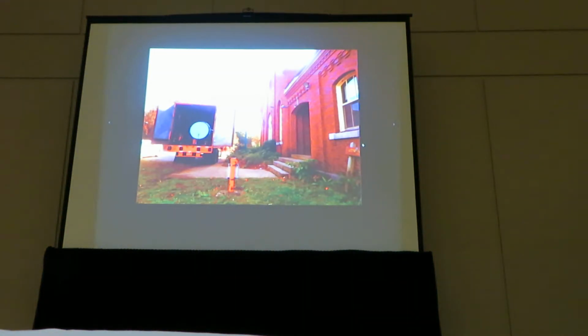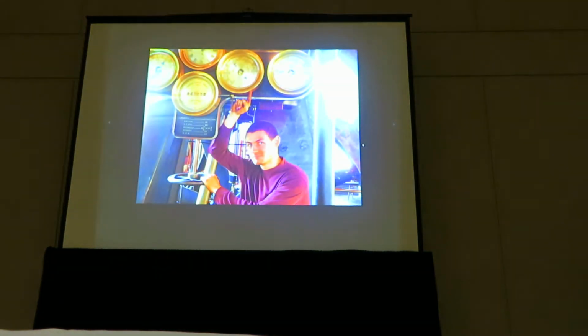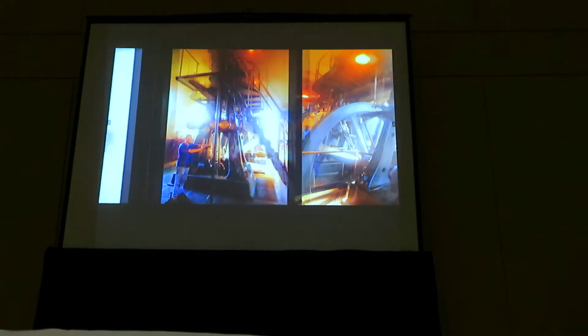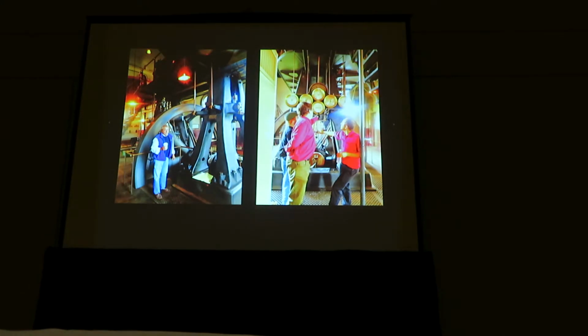And then another truck with another boiler showed up. I had arranged that. A very kind anonymous donor who Jerry knows brought the check in. Wilkinson Boiler brought us that boiler that parked outside, ran a hose in through the door. The gauges registered steam pressure for the first time apparently since 1933, and we got it spinning. And this went essentially without a hitch. It was just sitting there ready to wake up again. At first the top of the building filled with steam because we had an exhaust flange on that valve that I fixed leaking. After we repaired that, it was fine.